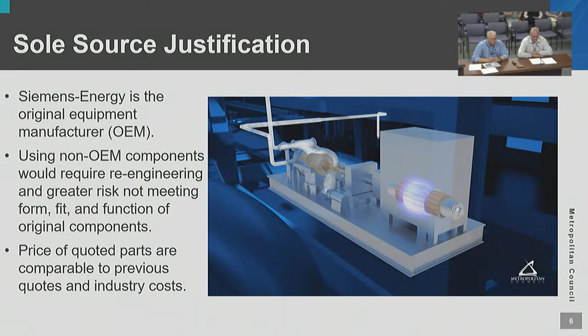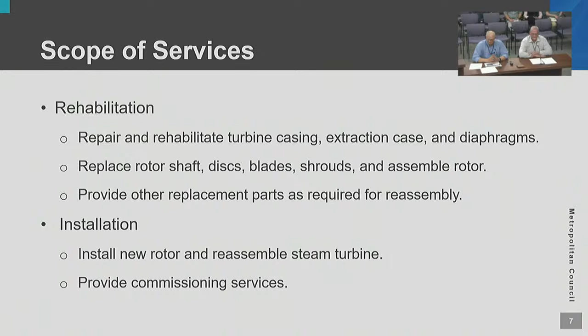The scope of services for this sole source is split into two parts. The first is the rehabilitation, centered around rehabilitating the turbine case, the extraction case, and the diaphragms, and replacing the rotor assembly including the shaft, discs, blades, and shrouds, as well as providing other parts as required for reassembly. The second part is the installation and oversight of commissioning, which involves installing the new rotor assembly, reassembling the steam turbine, and providing commissioning services in conjunction with our staff on site.